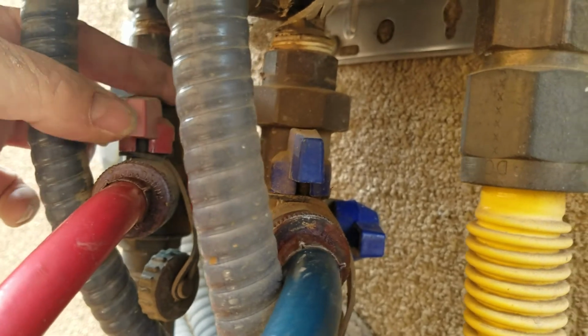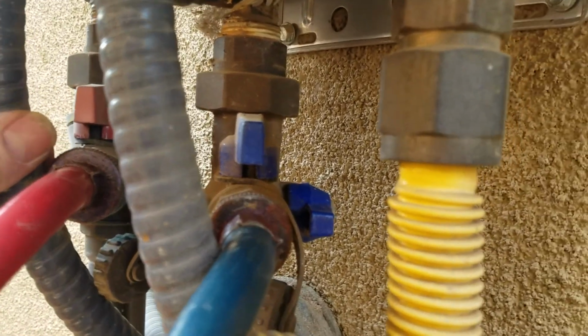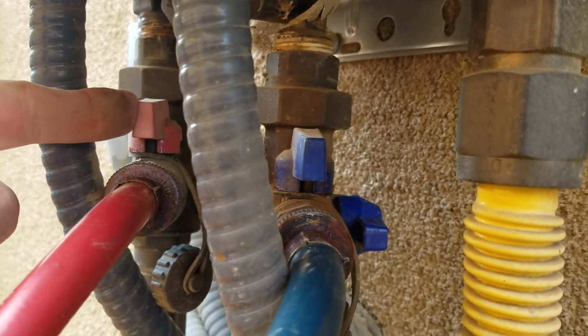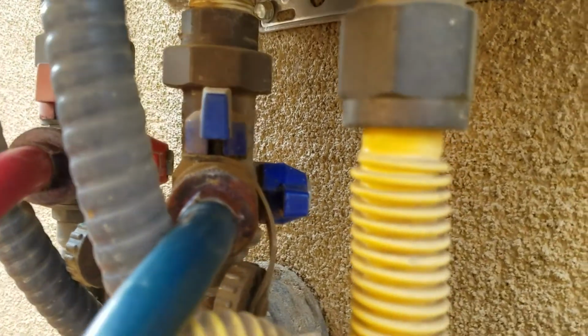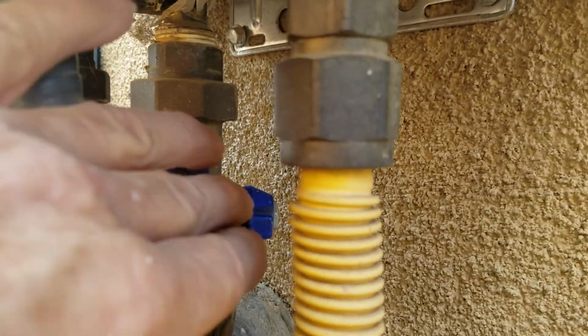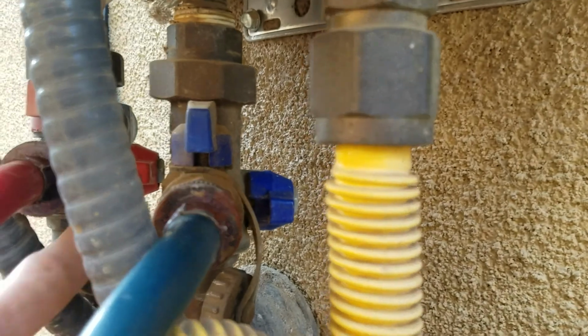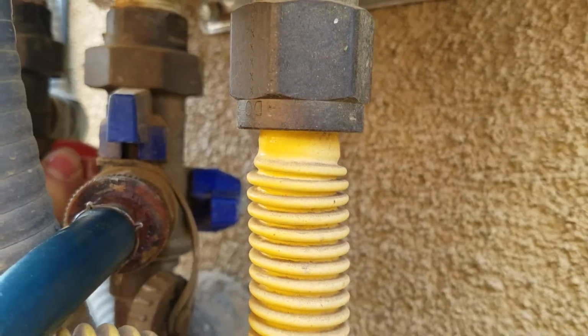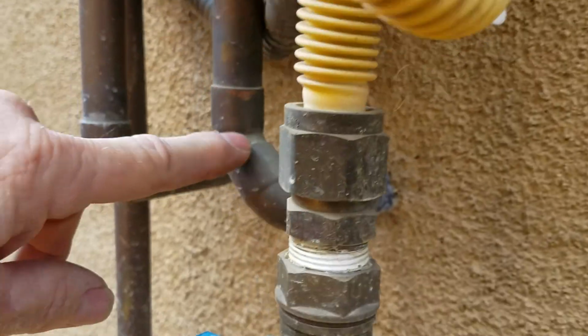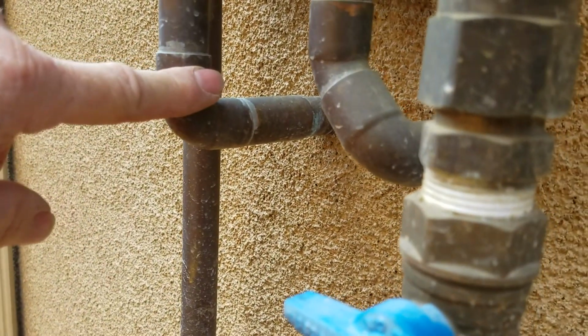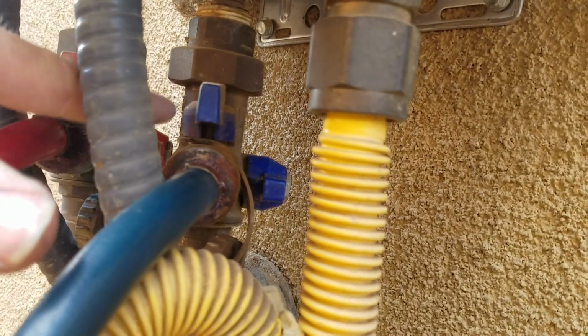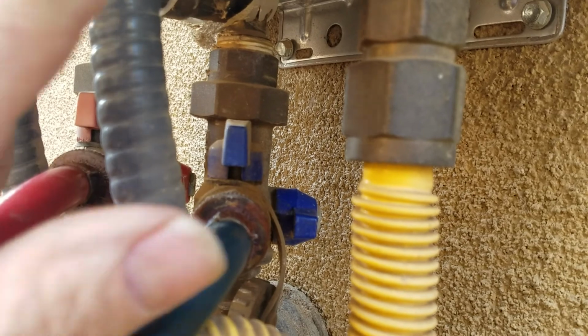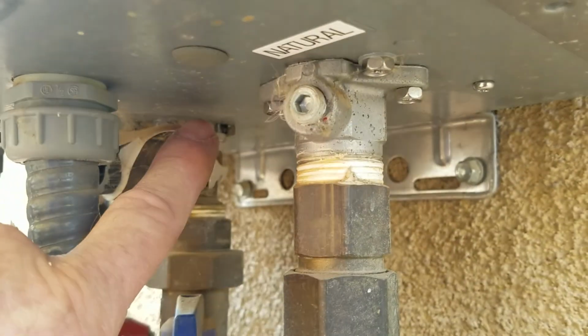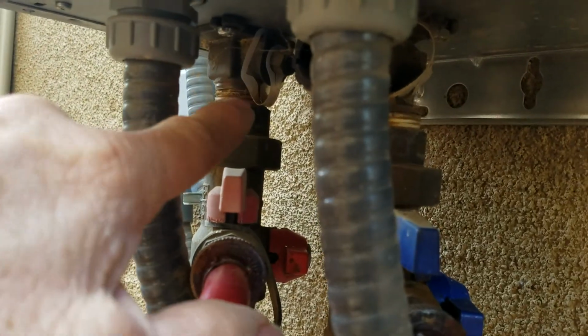Okay, so all you do is open these up. They're a little fussy because there's so much wiring going on around here, but open up the hot, open up the cold. The valves on the side - the one down here and the one over here - keep the vinegar from going back into the cold water system and into the home; they isolate it. What these two do is open up, and the cold goes up into the heat exchanger, comes back out and down through here through the hose, back down to the bucket.